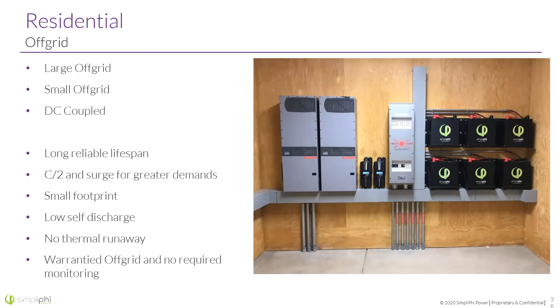Now, why does the SimpliPhi battery really make sense in a grid-tied battery backup system? We're talking about DC-coupled systems — this is almost a hybrid system, and really what Jake's talking about with the MorningStar 600-volt charge controller is dynamic DC charging, for greater efficiency while still maintaining functions like self-consumption, time of use, and backup — using that battery for multiple functions while also holding storage for when you need it, when the grid goes down.